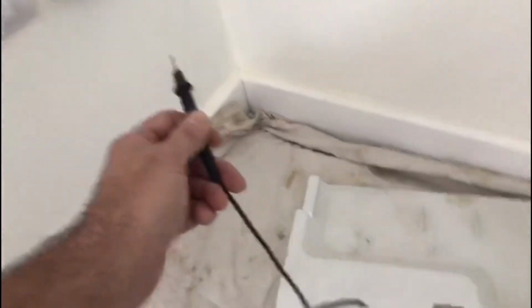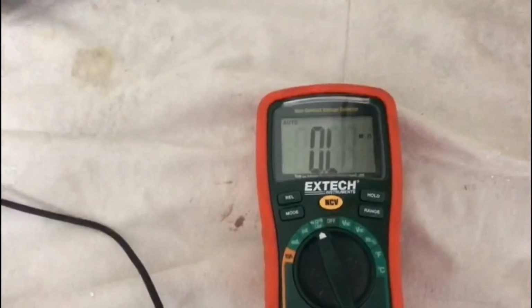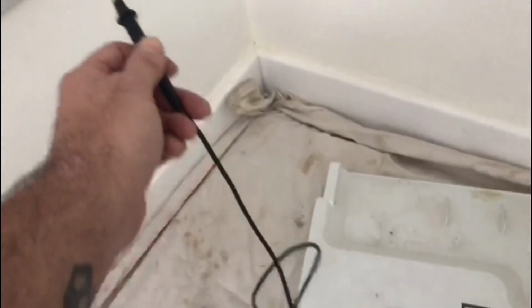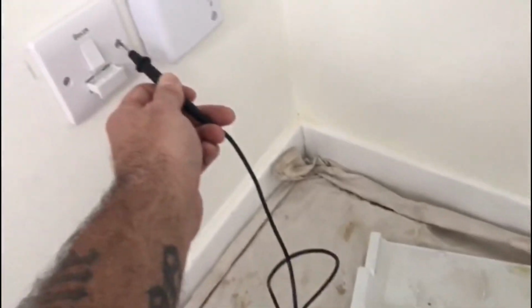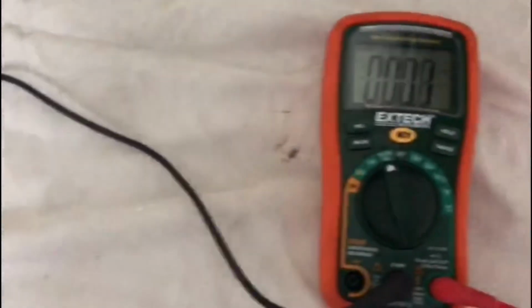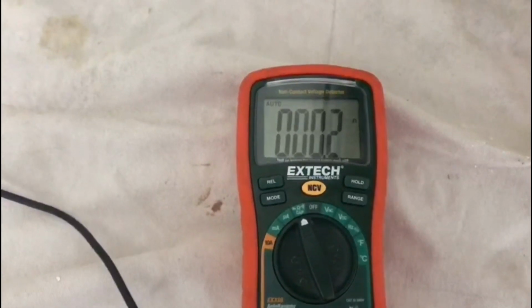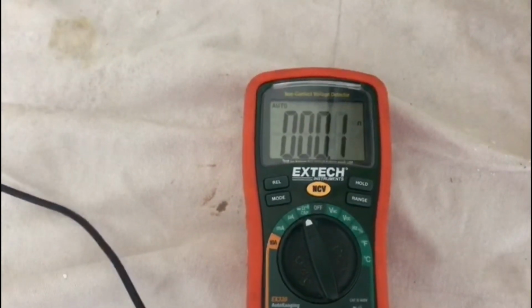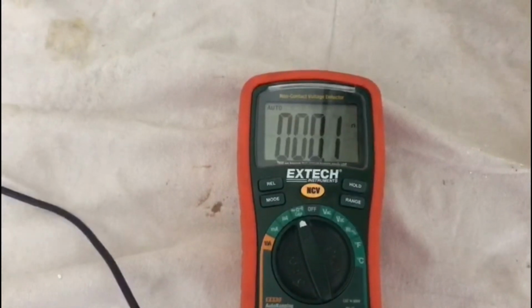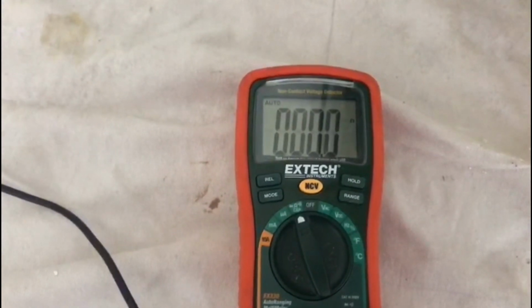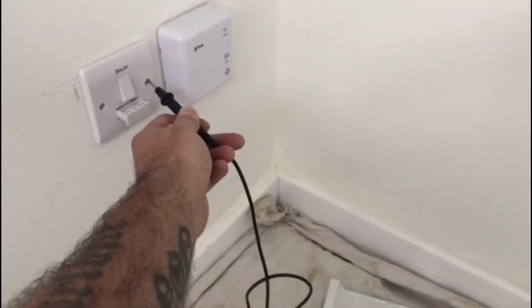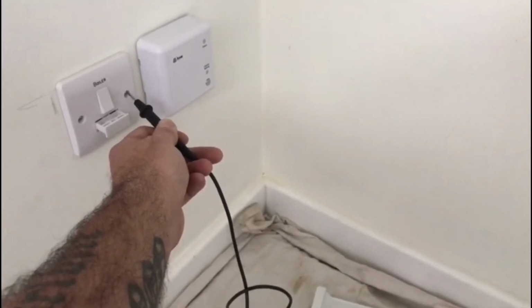If I take the black probe off, I'll have an open line. Put the black probe back on again on my earthing pin, I've got continuity again, the base reading on my multimeter. So I know, okay, the boiler is earthed properly to my house's earthing system. So that's the earth continuity check, checking from the earthing of your boiler to the earthing of your whole house system. That's the first dead check that you do.